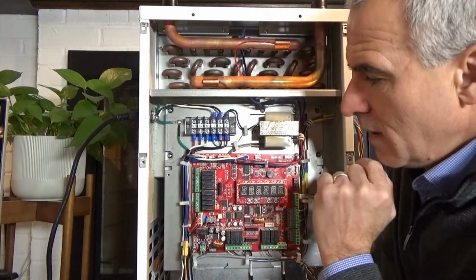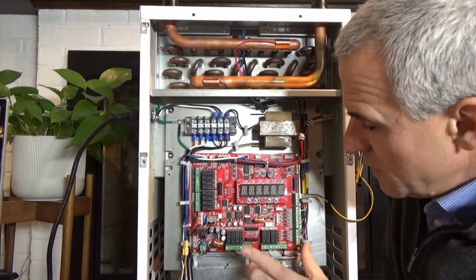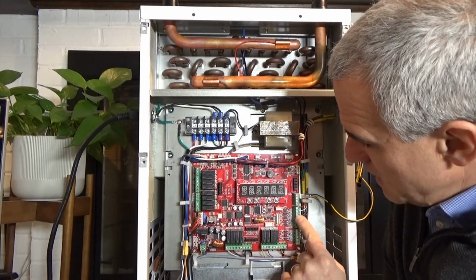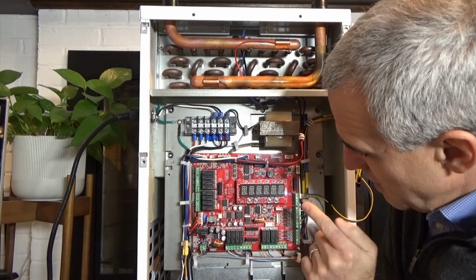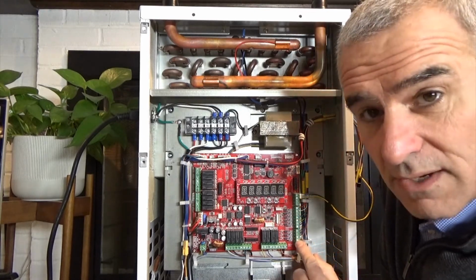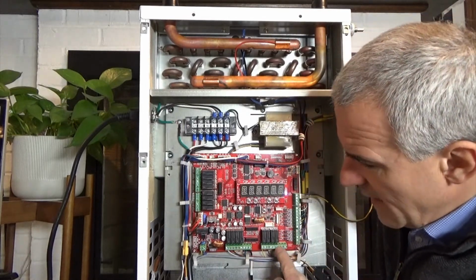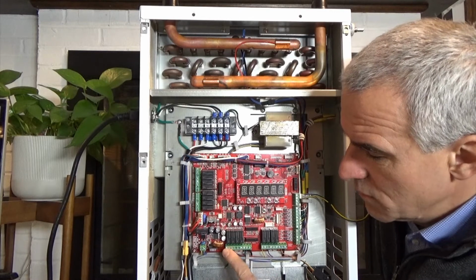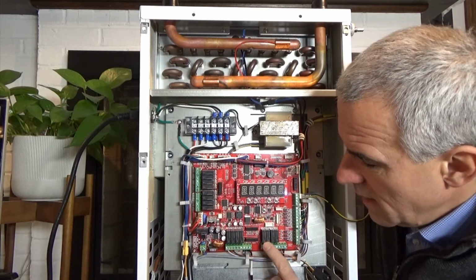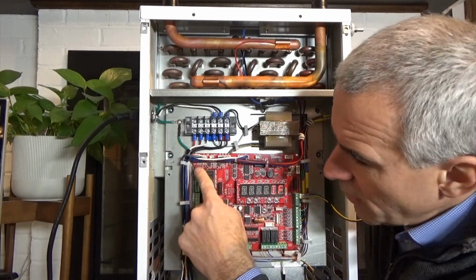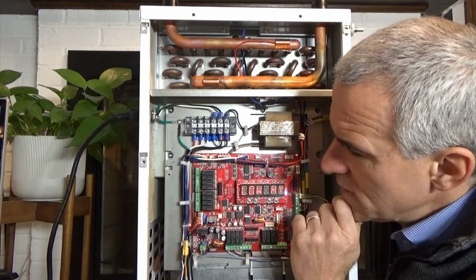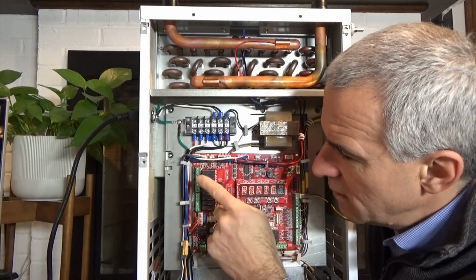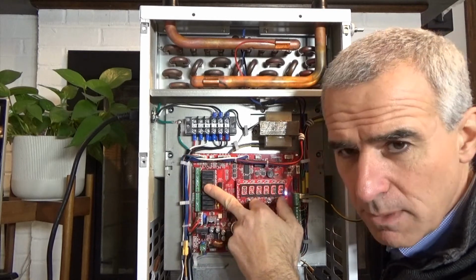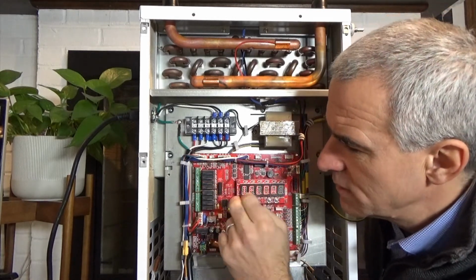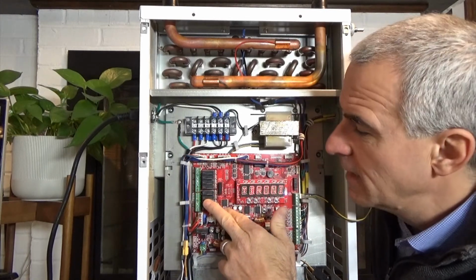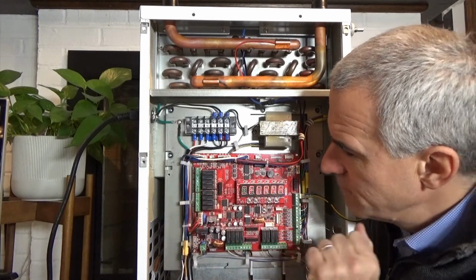In addition to the display, you have all of your inputs. So this is a 2-zone board. We've got our thermostat inputs here: our outdoor sensor, our flow sensor, thermostat for zone 1, thermostat for zone 2. On the bottom, we have our zone dampers. If we're using zone dampers, your zone dampers for zone 1, your zone dampers for zone 2. On the left, we have outputs. We have a circulator output, dehumidifier, humidifier contact. We have a heat pump for the reversing valve. We have those connections, and we have your AC compressor outputs as well, all on the right side.